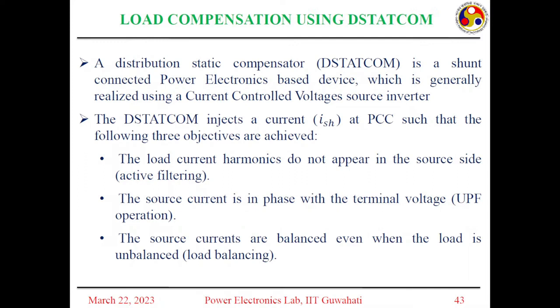In case of DSTATCOM, it is used in the distribution system, and we need to have more functionality here. It has to take care of voltage sags, voltage swells, or imbalance in the voltages, and also unbalanced source currents and harmonics in the source currents and so on. So DSTATCOM has more complexity compared to the STATCOM. Generally DSTATCOM is a power electronics based device. It contains a current controlled voltage source inverter, and it is a shunt type of device. It injects current at the point of common coupling so that these three objectives are achieved.